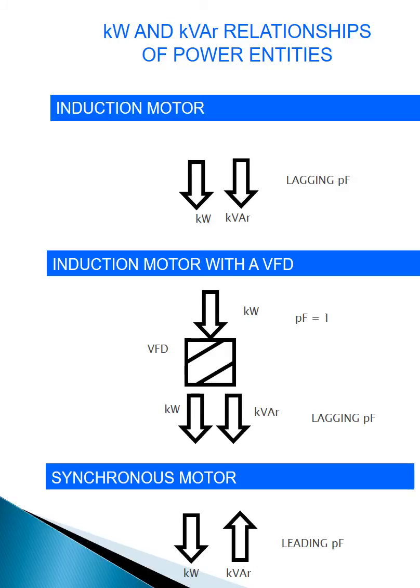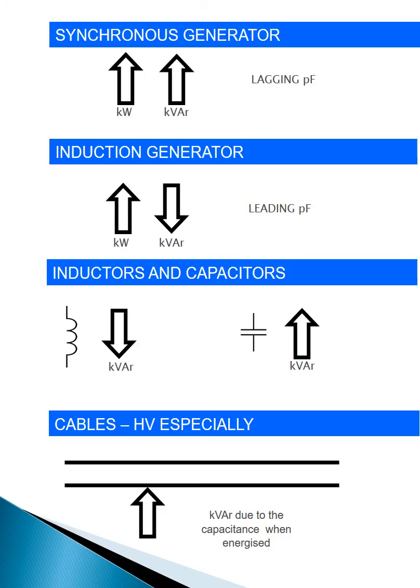The last example is a synchronous motor that has a leading power factor, and hence the reversal of the VAR from the induction motor representation. Here are another set of examples. For a synchronous generator operating in the lagging power factor mode, the kilowatt and kVAR vectors are both flowing out of the generator, as per our definition. An induction generator transmits kilowatts but absorbs kVARs, i.e. it has a leading power factor. The last three examples are the representation of items that provide or absorb VARs with no kilowatts involved.